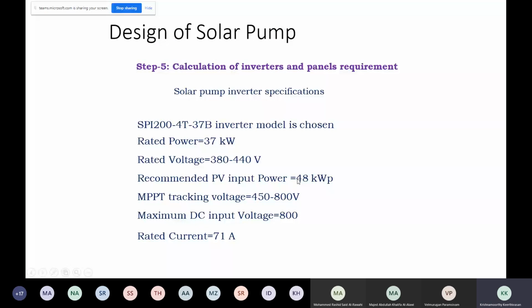Rated power 37 kilowatt. Usually the voltage, I told you, is 380 to 440. Different countries go for different standards: 400 volt 3 phase, 415 volt 3 phase, 440 volt 3 phase also available. And the recommended photovoltaic input, we just calculated, should be 48 kilowatt, taking into account the efficiency. Some 20% extra we will also calculate. Yesterday's calculation I explained to you.